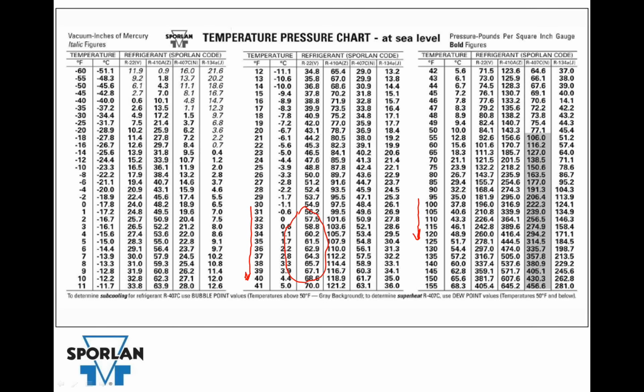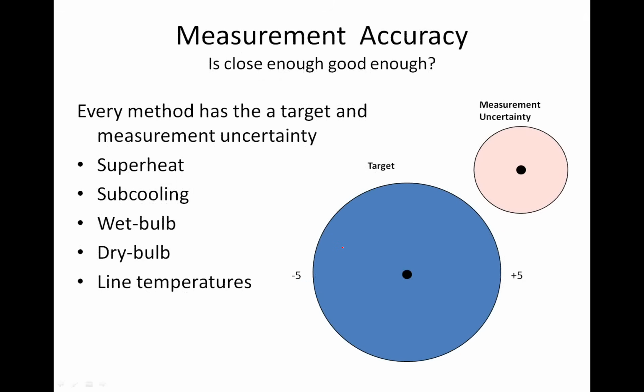So it becomes a challenge, and this is one of the big reasons that systems aren't charged properly. When you talk about measurement accuracy, it's really important that you understand that every measurement has a target and it has some measurement uncertainty. Okay, and what that means is, in this case, we say that we're plus or minus 5 degrees, and that's our target, right? And a lot of guys, if you've charged a system up before, you use the charging chart, it says, okay, you got to be within plus or minus 5 degrees.